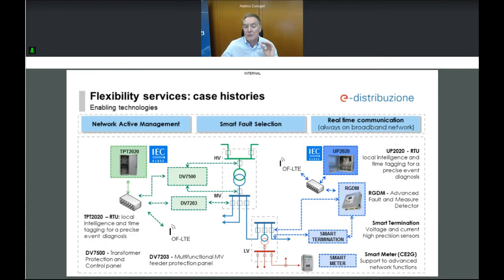Let's jump now to the technological side of the flexibility. On the top, you can see the advanced functionalities already online on the Puglia network. The advanced voltage regulation system applies optimization algorithms through the ADMS, using data collected from our new smart grid devices such as the RGDM and the open meter. The calculated optimal set point is then set by the new DV7500.